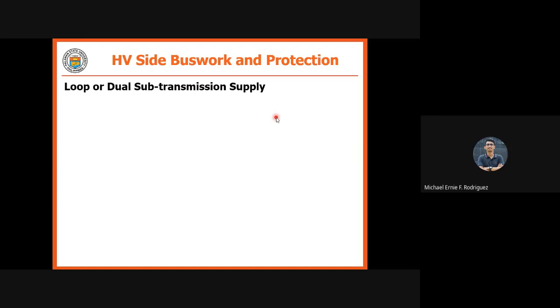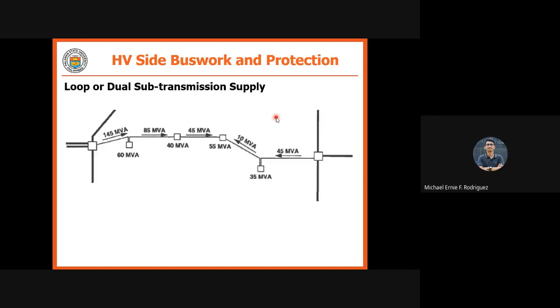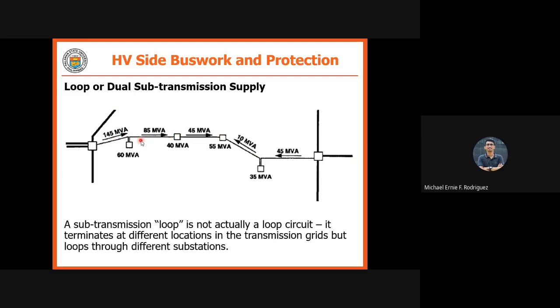Okay. And then we have the loop or dual subtransmission supply. So itong makapal na line, this is transmission system or transmission line. Okay, yung makapal na line, that is transmission line. Itong manipis na linya, this is a sub-transmission line. So, a sub-transmission loop is not actually a loop circuit. It terminates at different locations in the transmission grids but loops through different substations.